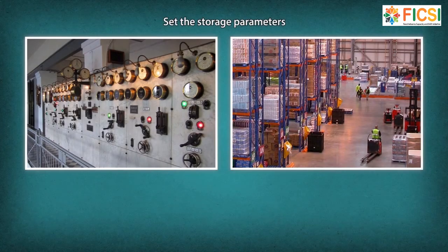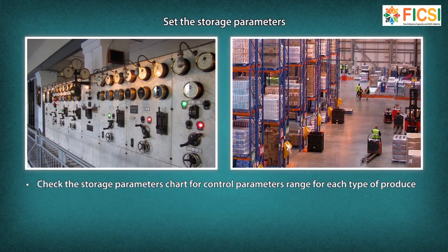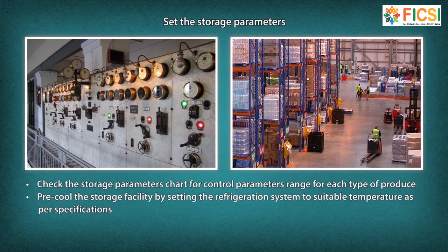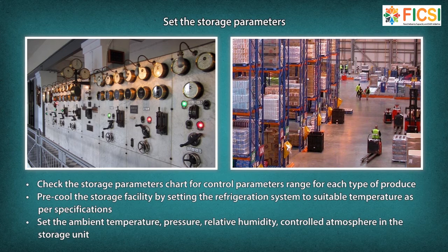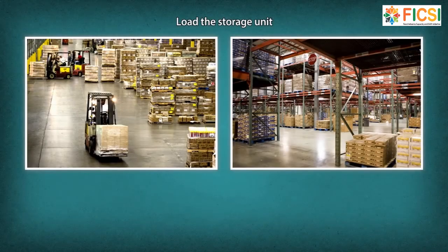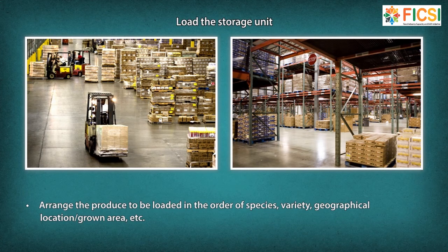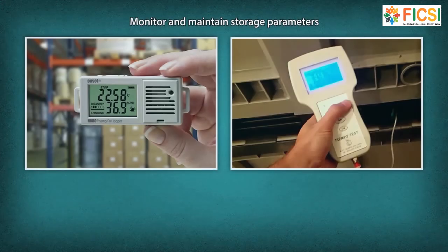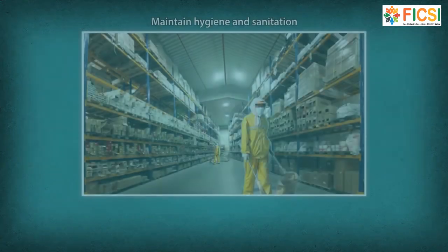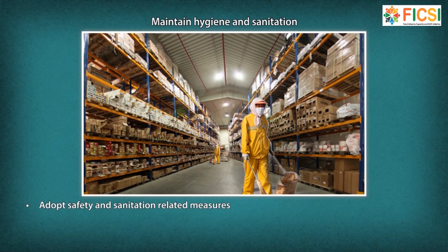Set the storage parameters. The technician checks the storage parameters chart for the control parameter range for each type of produce. They pre-cool the storage facility by setting the refrigeration system to suitable temperature as per specifications, and set the ambient temperature, pressure, relative humidity, and controlled atmosphere in the storage unit before loading.